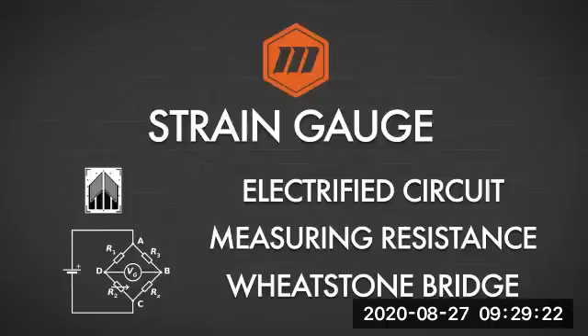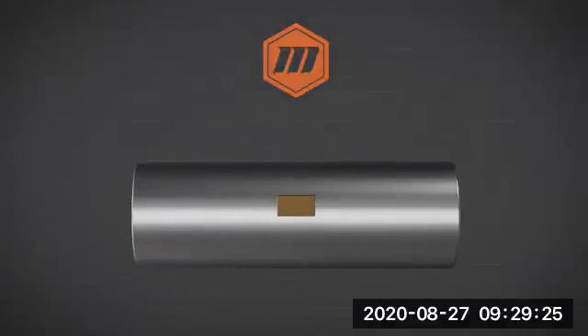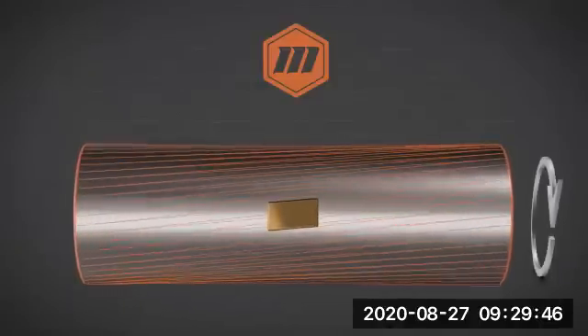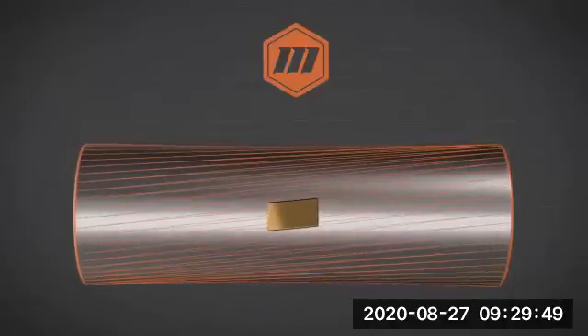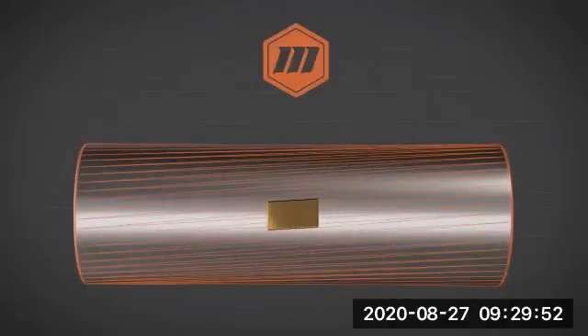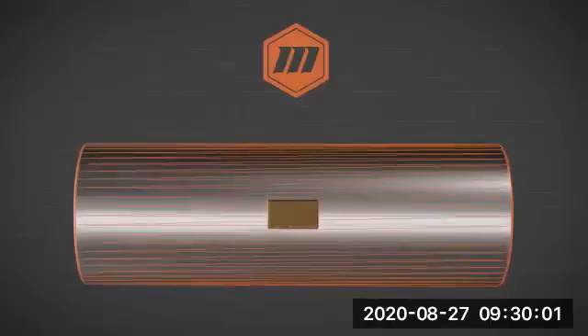So what that looks like if we were to use this in a graphical application: this is our link or substrate within the torque sensor. As we apply forces to the torque, we get a torsional change within the element, and you can see the strain gauge flexing and moving, which is how we measure the resistance we see in our readings.